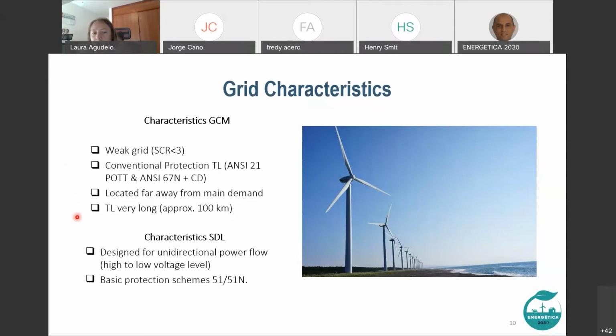I would like to mention too the distribution system. As I showed you in the last slide, there is a very important percentage of this kind of generation in the distribution system. And it is important to mention that the distribution system was designed for unidirectional power flow. The flow is typically from high to low voltage level, and distributed generation involves bidirectional flows. This is a very important challenge for this voltage level. Another very important thing in the distribution system is the protection scheme. They are basically non-directional overcurrent.